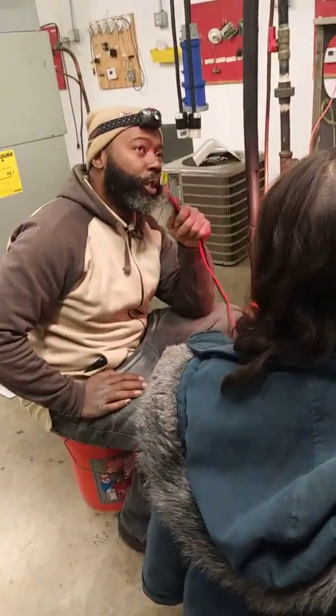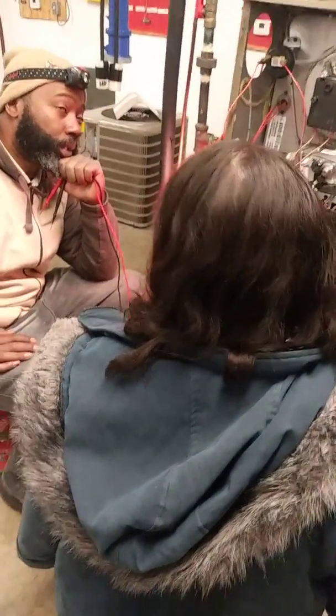So if the gas valve clicked, are we getting 24 volts in the gas valve? Not necessarily. I don't think so. Well, the gas valve clicked. Yeah, you're getting 24 volts because it's... I don't know, that's what we have to check. There's a lot of disconnected wires. Yeah, that's what I'm saying.